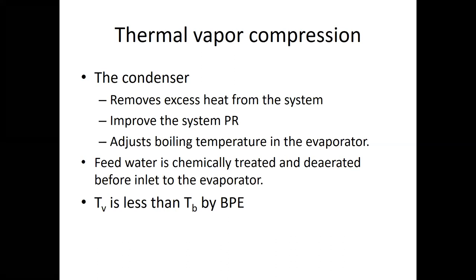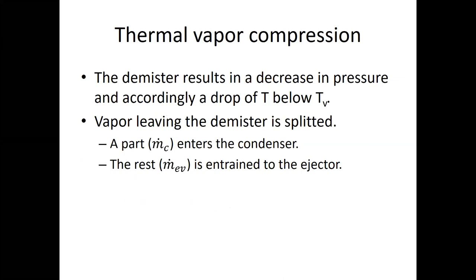The BPE can be calculated by correlations or using the Engineering Equation Solver as a function of saline water temperature, salinity, and pressure. The mist eliminator, or demister, causes a small pressure decrease, which in practice reduces the temperature slightly below TV; in our calculations we neglect this. The vapor leaving the mist eliminator is split: part goes to the condenser as M-dot C, and the rest as M-dot entrained vapor is entrained into the ejector. So M-dot C plus M-dot entrained vapor equals M-dot vapor, the total distillate obtained from the unit.